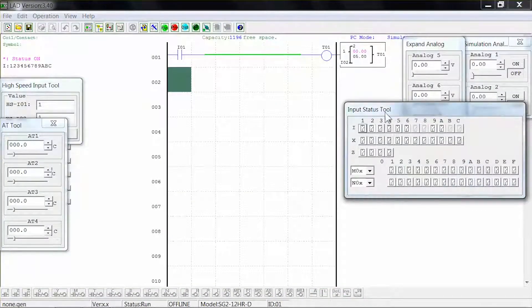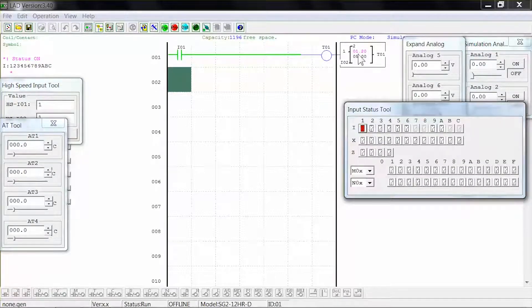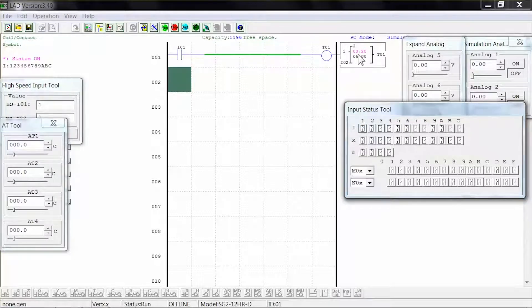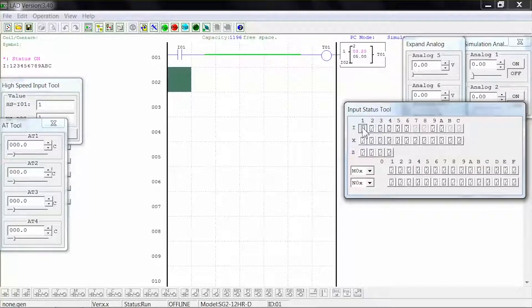In our input status tool we can select digital input 1 and the timer starts to count. If we deselect input 1, the timer stops counting but maintains the time elapsed. If we select input 1 again, the timer continues to count from that time and at 5 seconds the coil activates.